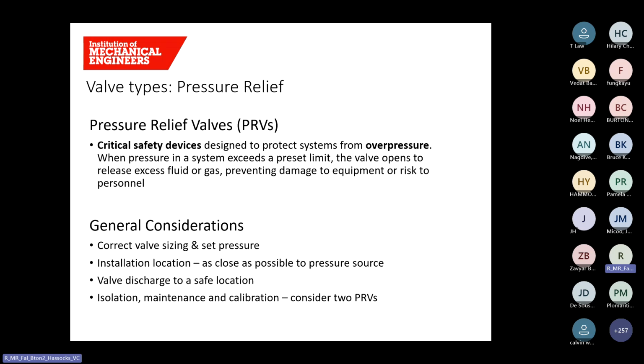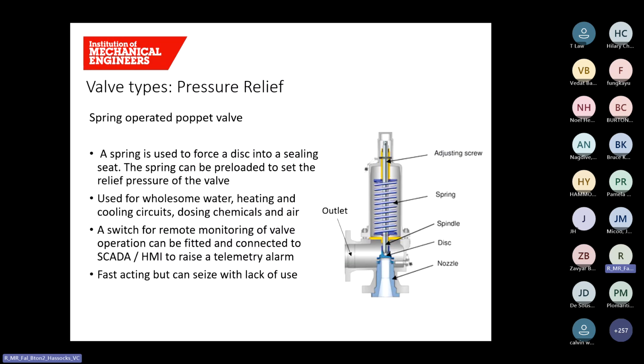You can use things like a 3-port valve or similar switchover mechanisms, and that ensures at least one PRV remains online at all times, thus maintaining continuous protection. A spring-operated poppet relief valve is a direct-acting safety device. It uses a spring-loaded poppet mechanism to force a disc into a sealing seat. The relief pressure of the valve is determined by adjusting the preload on the spring.